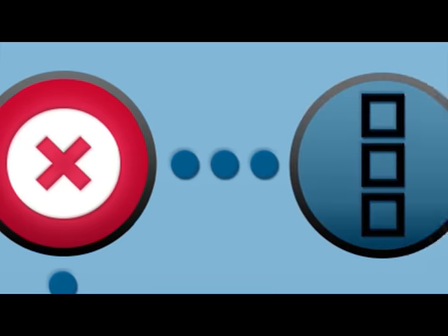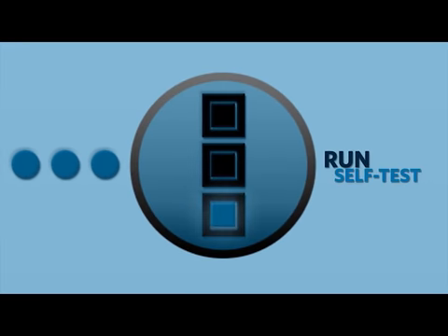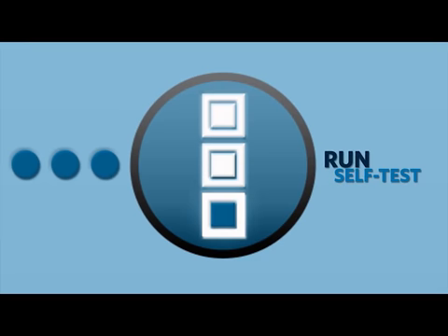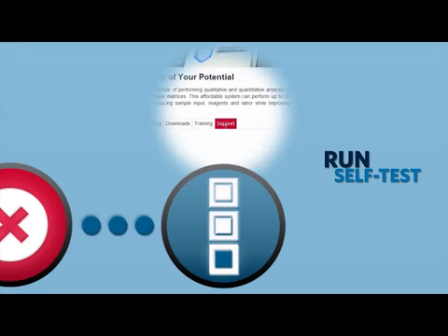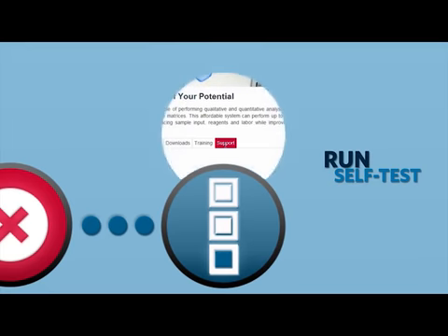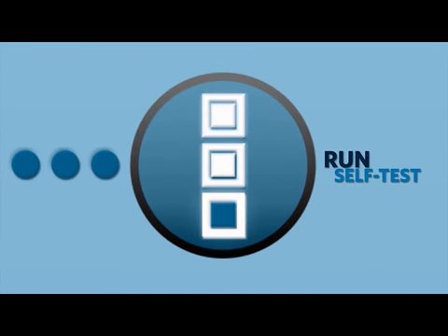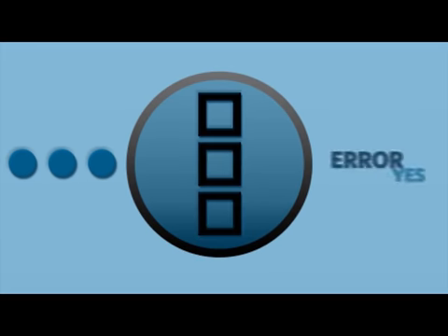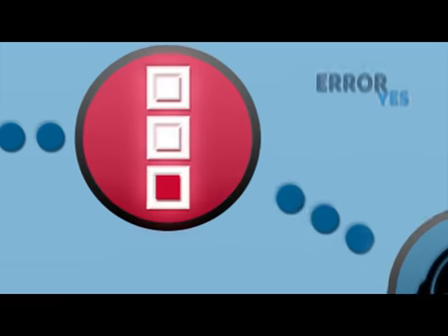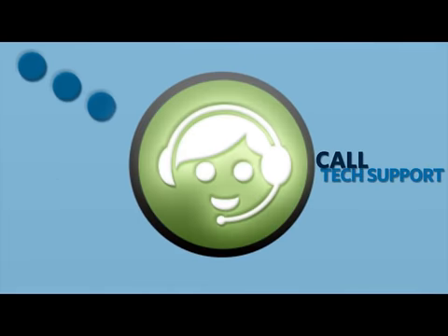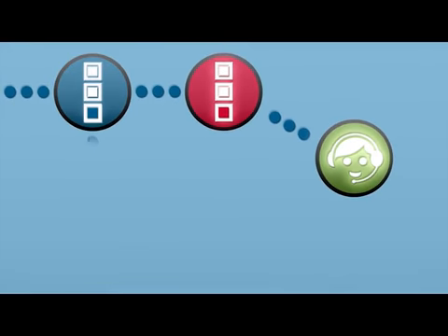The second step in the basic troubleshooting for your MagPix instrument is to run the self-test. Again, if you're not sure how to do this, refer to the corresponding video on the Support tab of the MagPix instrument page. The self-test will check all hardware functions. Any problems will be detected. If the self-test fails, collect the error and call technical support. Advanced troubleshooting is required. For more information on getting the error, refer to the support video. If the self-test passes, the hardware is working properly.